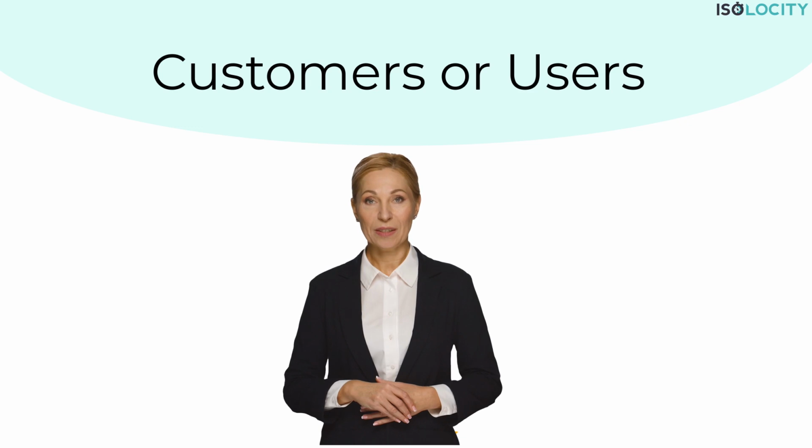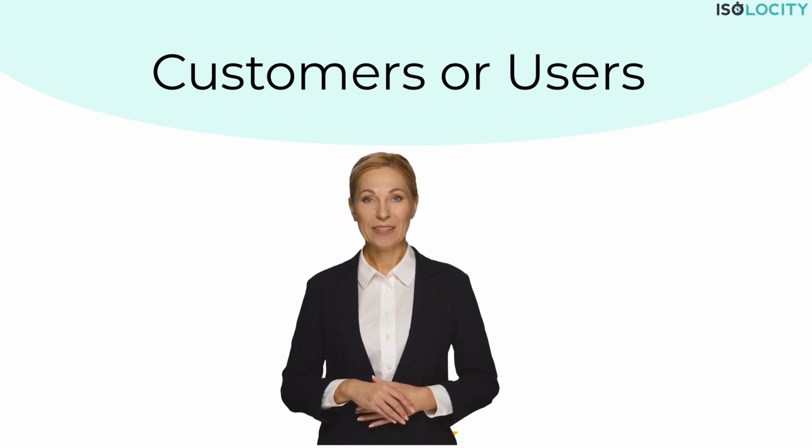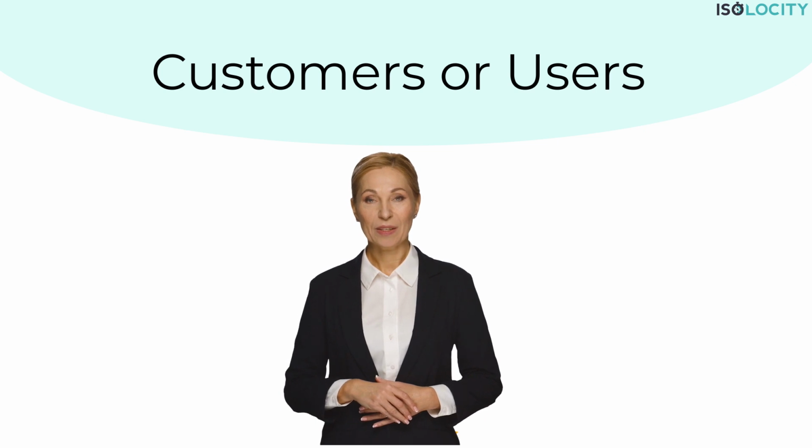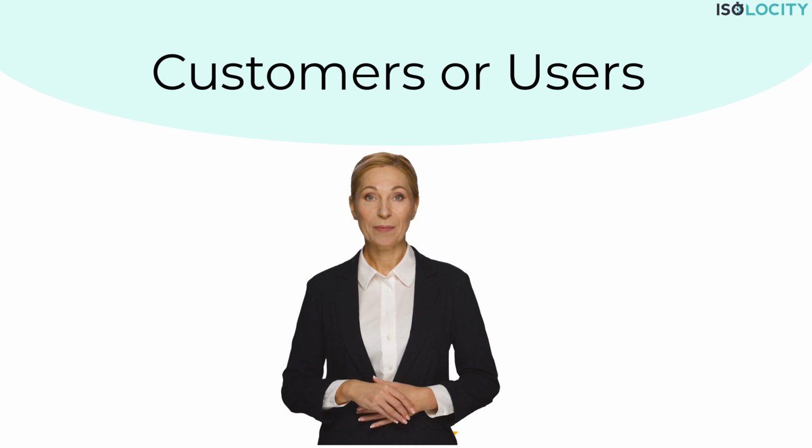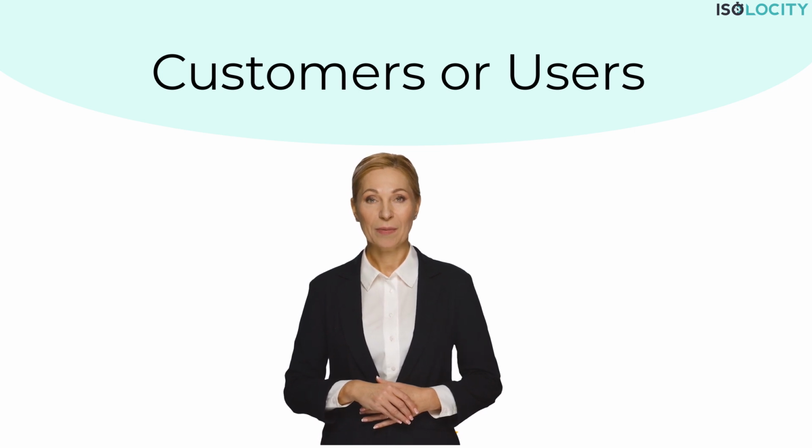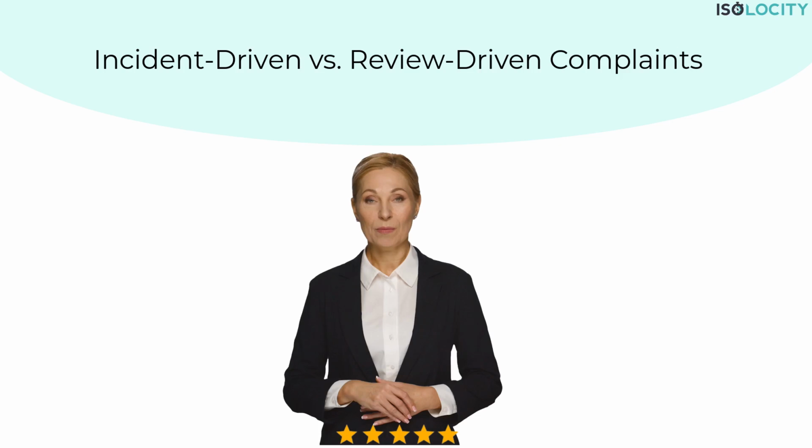Customers or users. Direct feedback from those using your product. Healthcare providers, doctors, nurses, or other professionals who notice product issues during use. Regulators, health authorities or industry regulators might flag non-compliance issues. Internal reviews. Your own audits and quality checks may uncover potential problems. Post-market surveillance. This involves ongoing monitoring of devices after they've hit the market.